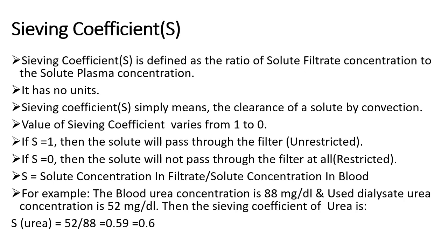Another important characteristic is the sieving coefficient, also known as S. Sieving coefficient is defined as the ratio of solute filtrate concentration to solute plasma concentration. You can calculate it by dividing the solute concentration in the dialysate by the solute concentration in the blood. That is your sieving coefficient — it has no units.